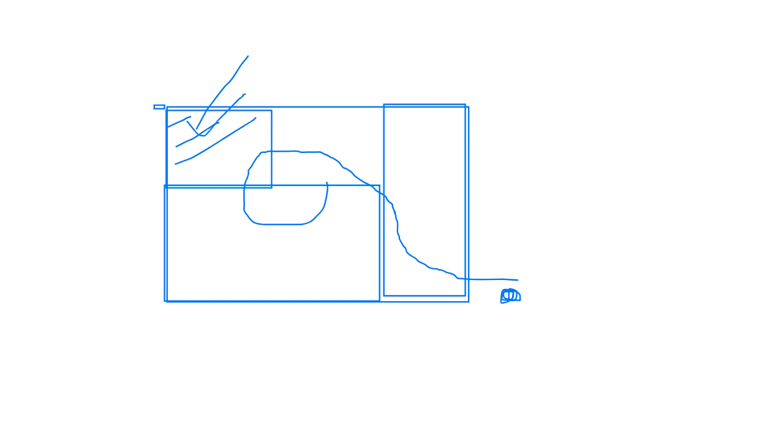As I said, this is the office area, so it must be light hazard occupancies, LH, and this is the storage area. It might be extra hazard occupancies, and this is the production area. It might be ordinary hazard areas. Now the most remote area cannot be the most demanding area in this case, because at light hazard, this is the most remote area, but the extra hazard areas have a higher discharge density.